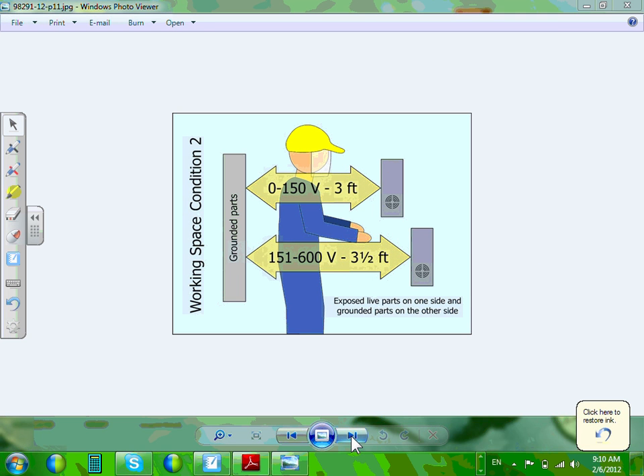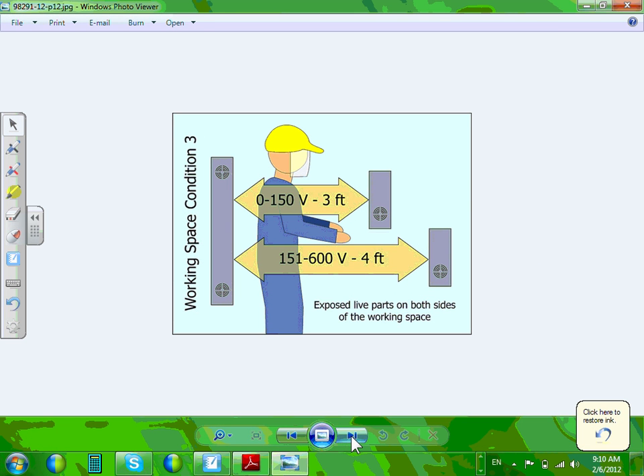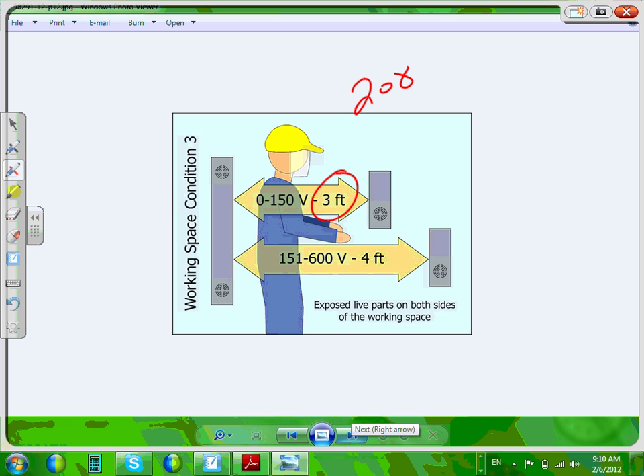The last one, so we added the last one, guys, if you have energized equipment. You have energized equipment, look at this. Baby system, I call it the baby system, 208 or 240. This system continues to be 3 feet, no matter what. 208, like our system, Chris, right now, regardless of what's in front of the panel. What is it? Because we have 208/120, you're going to end up with 3 feet no matter what. You jump into the 480, 600 volt system, then what do you get? You get 4 feet. So to summarize, guys, for 208/120 and 240/120, 3 feet no matter what.